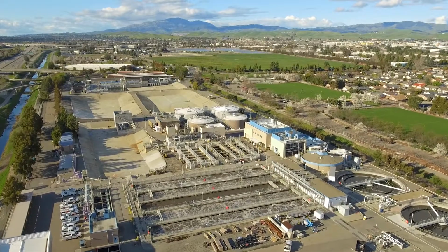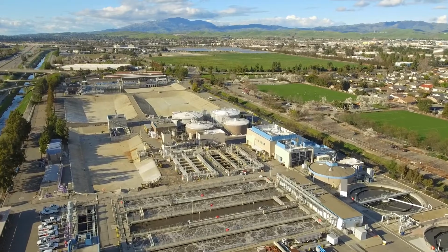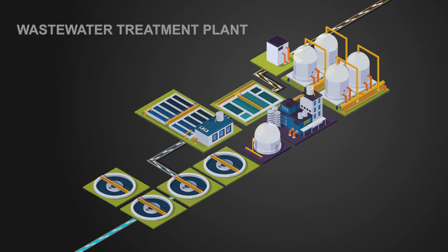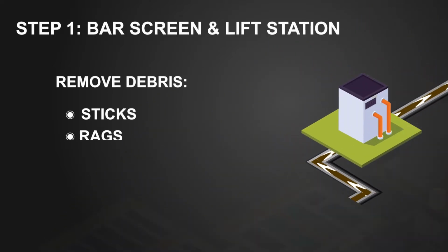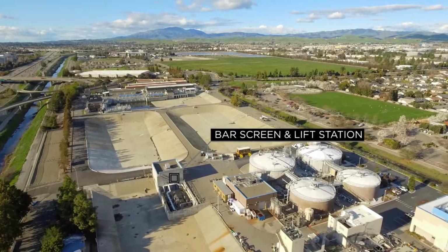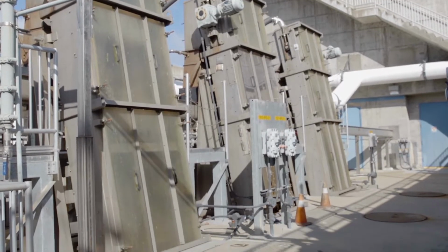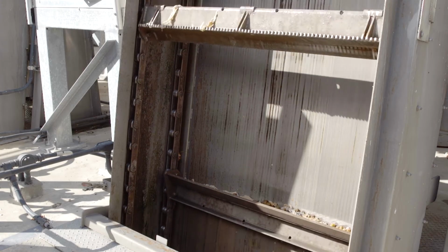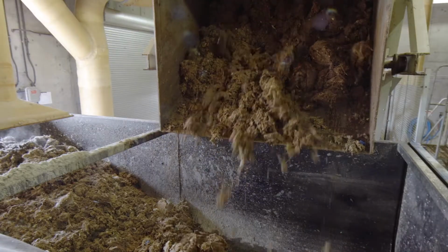Once the wastewater gets to the treatment plant, we have to try to remove all of the material that can clog up pumps or be corrosive to pipes. So the first material that we remove is called wastewater screenings. And screenings is things like sticks, rags, diapers, anything like that that can clog up our equipment. So we have these automated screens. The wastewater runs through these automated screens and all of that material gets clogged up on those screens, and then it's raked off. The moisture is compressed out of it and it's put in a dumpster and hauled away like the garbage from your home.